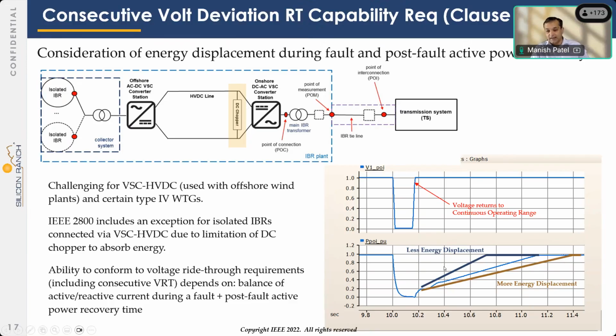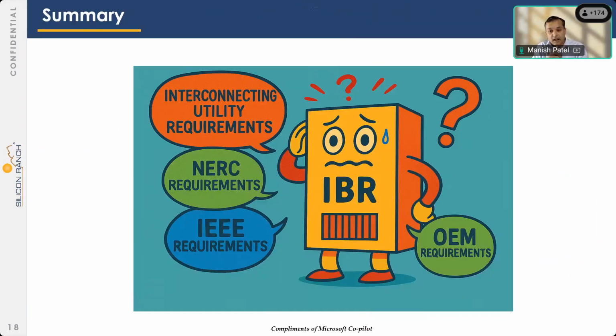That can then be extended. What is the active power recovery time? Is it 1 second, 2 seconds, 5 seconds? Depending on the active power recovery time, this DC chopper is, for example, absorbing power, right? So all this needs to be thought through. Maybe in the next revision of the standard, we understand energy displacement a little better, what IBRs are able to absorb in terms of energy displacement, and then write up voltage ride-through and consecutive voltage dip requirements accordingly. And with that said, this is my last slide.